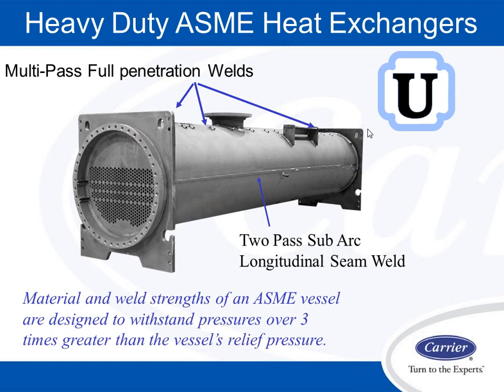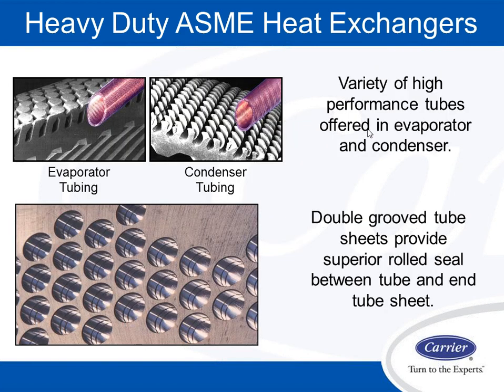Heavy ASME duty pressure vessels. Like most people who make 134A designs, it's an ASME pressure vessel. These are what I call the little things. You can see here on the top we have our evaporator tubes and our condenser tubes. But if you look at the bottom picture, it's a dual grooved tube sheet.